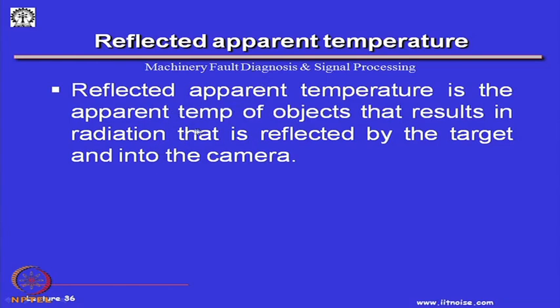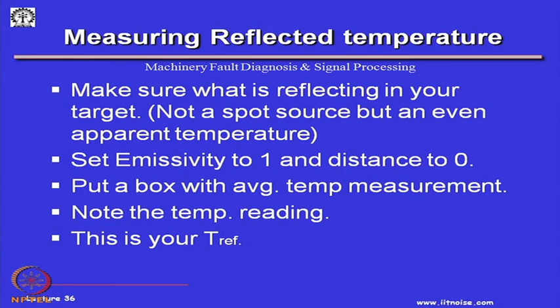So the reflected temperature is a problem while doing IR measurements. The reflected apparent temperature is the apparent temperature of an object that results in radiation reflected by the target and into the camera. To avoid reflections, we should not be right in front of the camera, we should be a little away from it. So make sure that what is reflecting in your target is not a spot source, but an apparent temperature over an area.